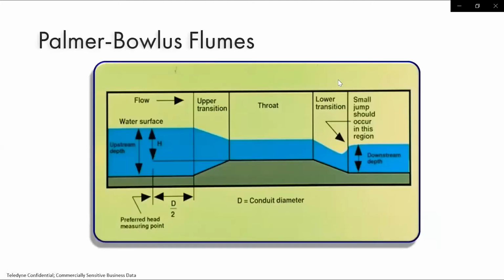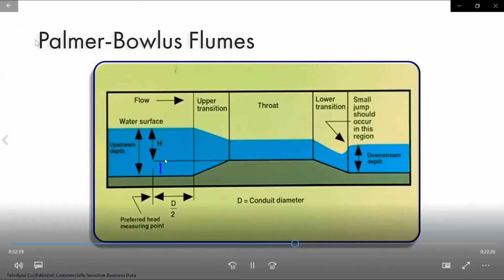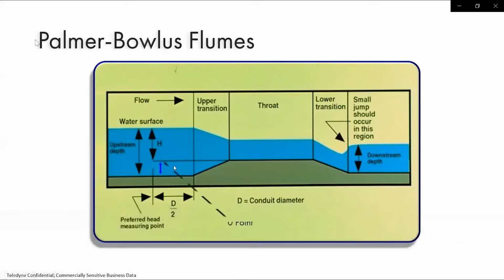And then it's going to be a very repeatable and accurate way to measure your water depth. Now the Palmer-Bowlus Flume, you can use the same techniques, but I bring this up just because there's always this potential for error. The difference with the Palmer-Bowlus is that it has this riser here. And so this is the 0 point. And so you need to keep in mind what this offset is.